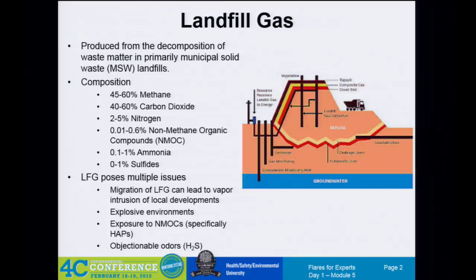They do have some interesting gas combinations. What's really cool is the concentration of CO2 can be really, really high, and the methane numbers obviously are high. What they do is put these blowers or vacuums that basically suck the air out of the landfill and send it to a combustion device. Naturally you have to supplement it because sometimes it's not combustible on its own. There are some fun, interesting problems with landfill gases, including the odors - not just odors, but H2S odors. They don't use chemical plant refinery type operators at landfills, so they're kind of prone to this problem of blowing up their flares, blowing up their blowers. They're not as attentive to combustible mixtures as you are at your plant. Let's just put it that way.